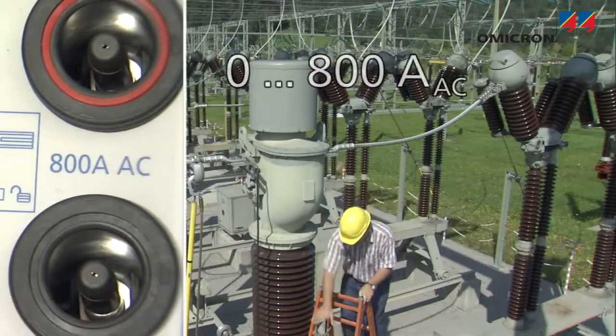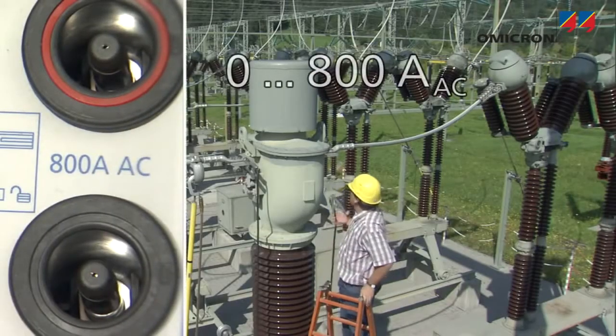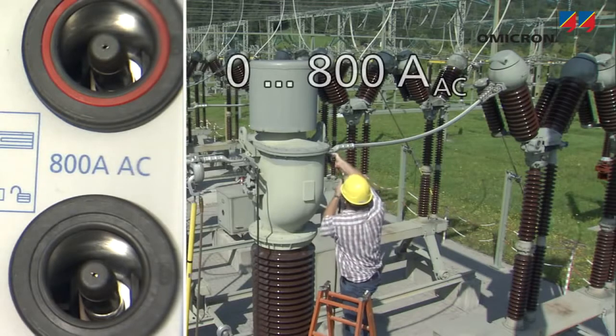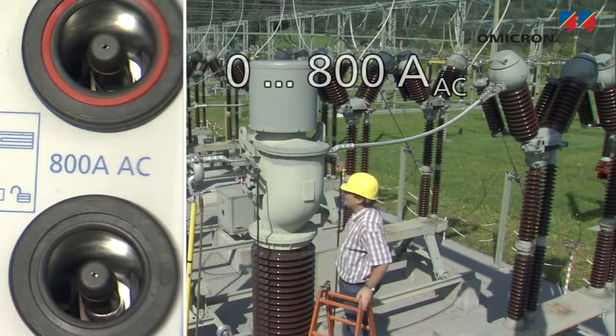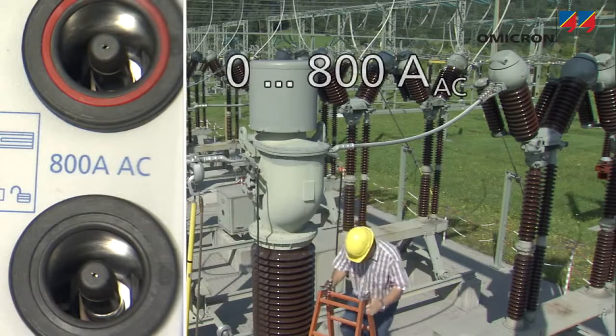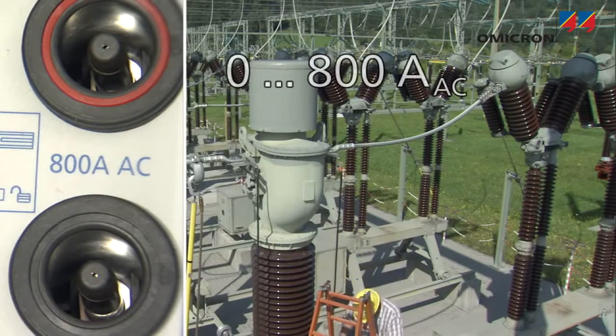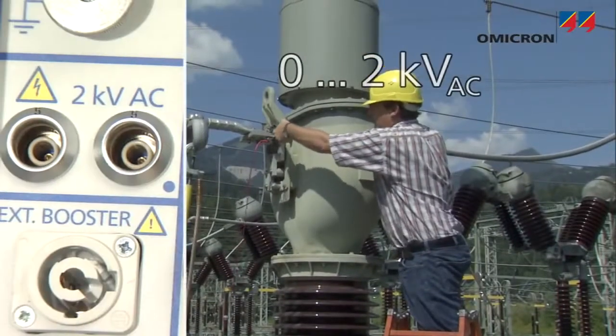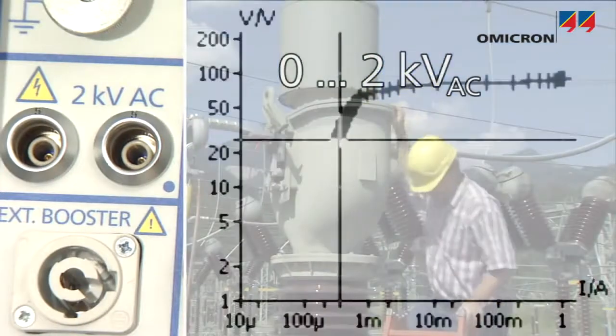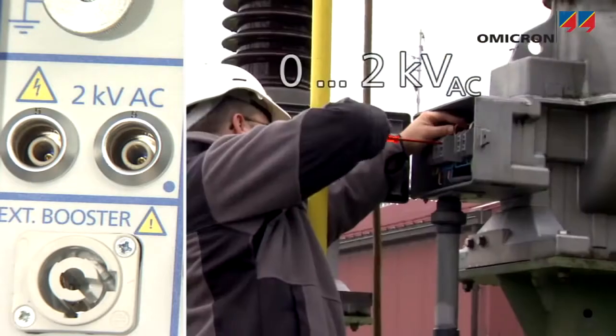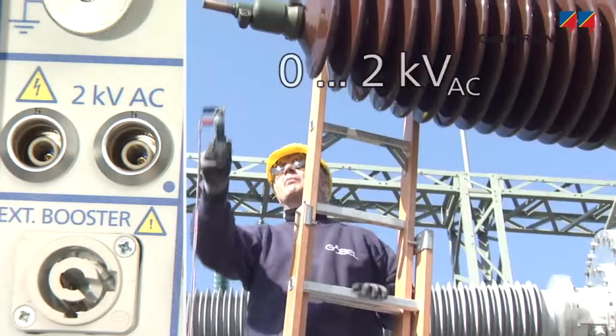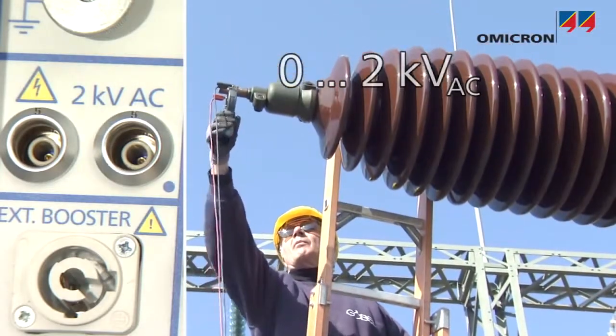The 800 amp high current output is mainly intended for testing current transformers. The CPC also verifies the CT's polarity by comparing the phase angles of primary and secondary current. Its high voltage output generates up to 2000 volts and is used to record a CT's magnetization curve, test a VT, or perform transformer ratio measurements.